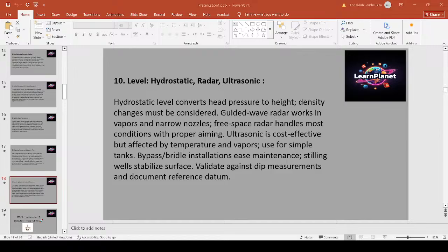Hydrostatic level uses head pressure, so if density varies with temperature or composition, it must be compensated. Guided wave radar works in vapors and narrow nozzles and is great for interface measurement in stratified fluids. Free space radar is ideal for tall tanks where aiming and blind zones are managed. Ultrasonic is low cost but affected by vapors, foam, and temperature shifts. Use stilling wells or bridles to steady surfaces and allow maintenance without opening the vessel. Example: for a crude oil tank with vapor and foam, choose guided wave radar with a stilling tube and configure the dielectric setting for oil.